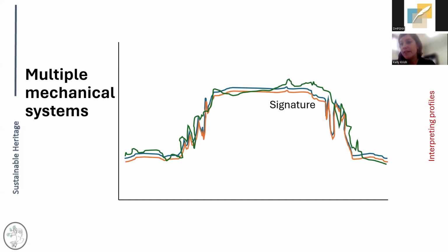We can use this to find out which air handlers are serving which spaces if you don't already know. That makes it a lot easier if we're talking about making changes. We can know which spaces will be impacted. Or if you see the same issue across multiple spaces, it could be tied to a single air handler that needs to be addressed. So in this example, the blue and the orange line have very similar signatures. Even though they're not always exactly the same, it's generally the same pattern, pretty close to the same lines. Green, on the other hand, is showing a different type of signature. Generally it's still the same path, but it's not consistent enough, and we probably consider that it has a different air handler serving it.